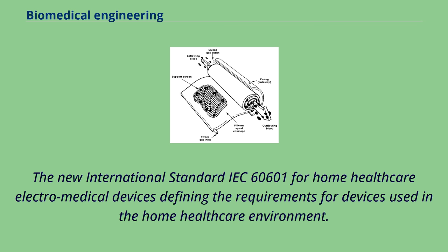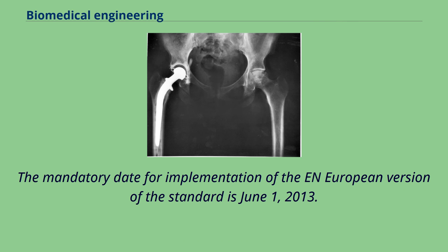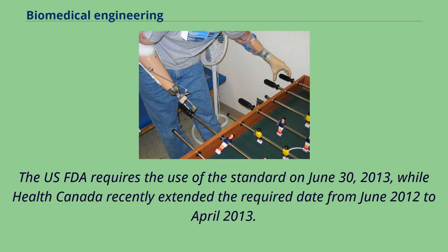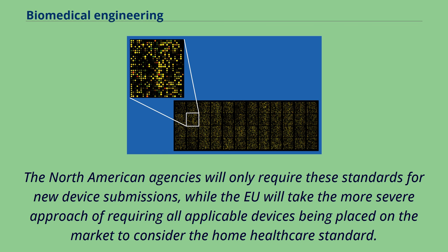The new international standard IEC 60601 for home healthcare electro-medical devices defines the requirements for devices used in the home healthcare environment. IEC 60601-1-11 must now be incorporated into the design and verification of a wide range of home use and point-of-care medical devices, along with other applicable standards in the IEC 60601 3rd edition series. The mandatory date for implementation of the European version of the standard is June 1, 2013. The US FDA requires use of the standard by June 30, 2013, while Health Canada extended the required date from June 2012 to April 2013. The EU will take the more severe approach of requiring all applicable devices being placed on the market to consider the home healthcare standard.